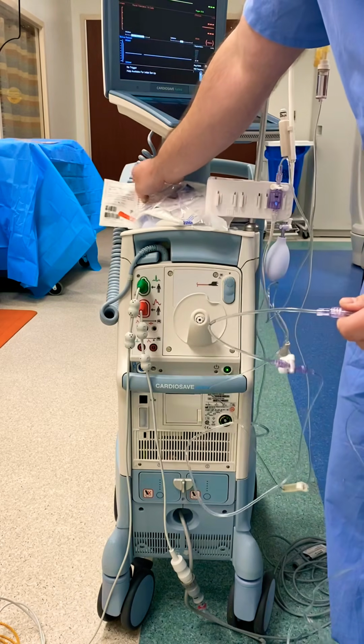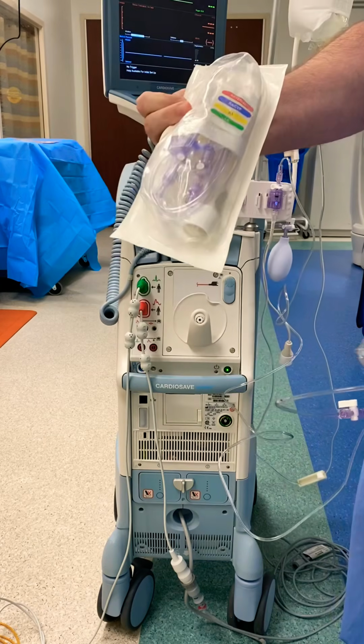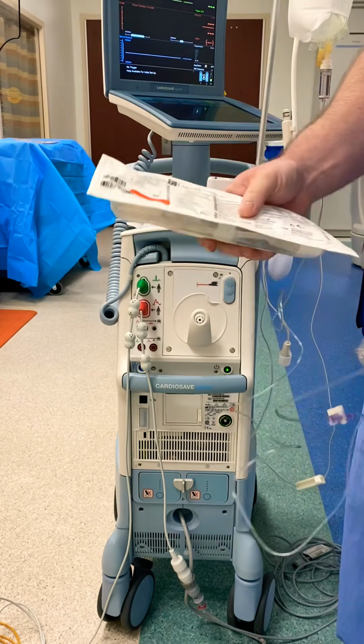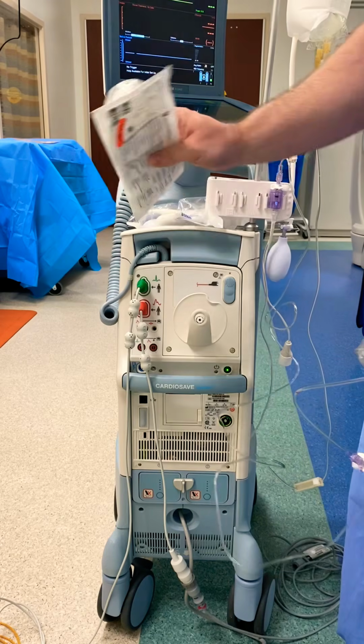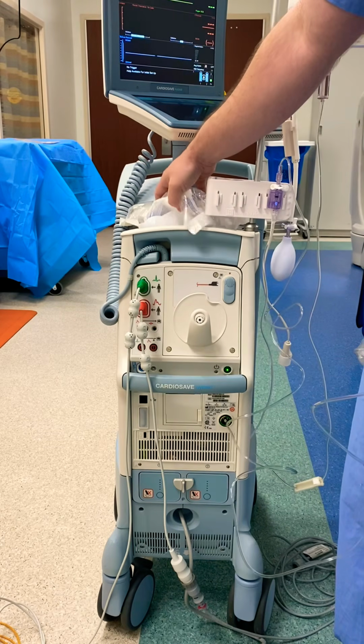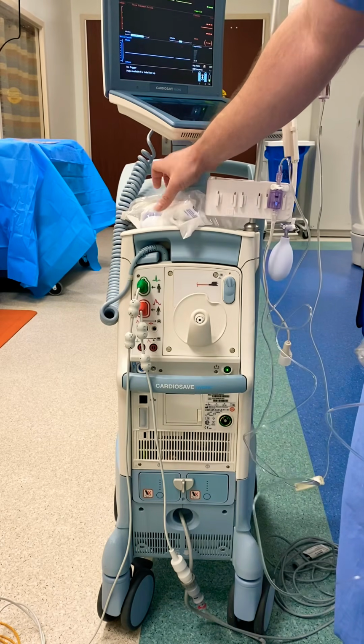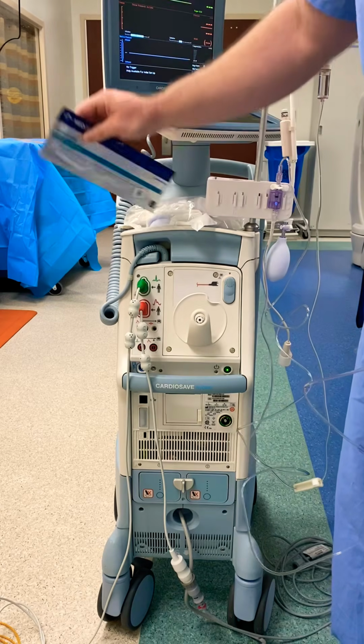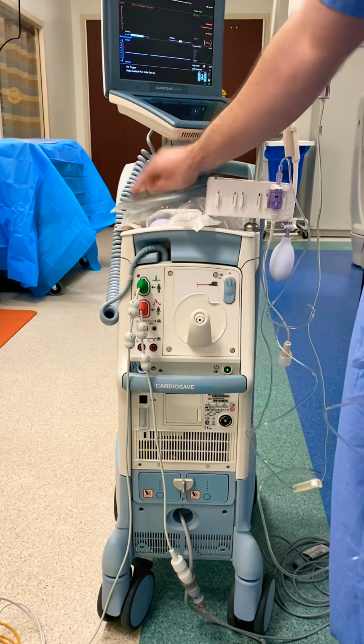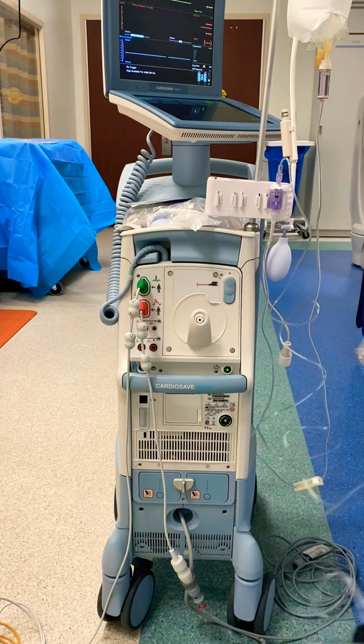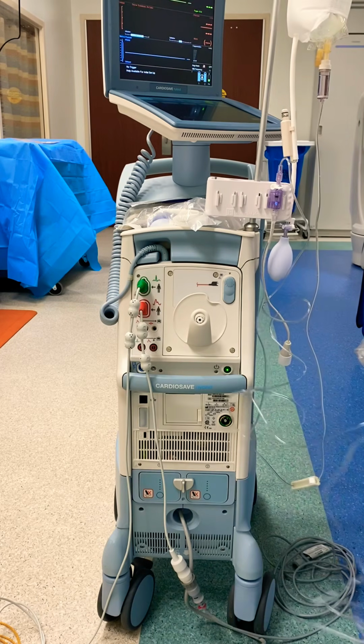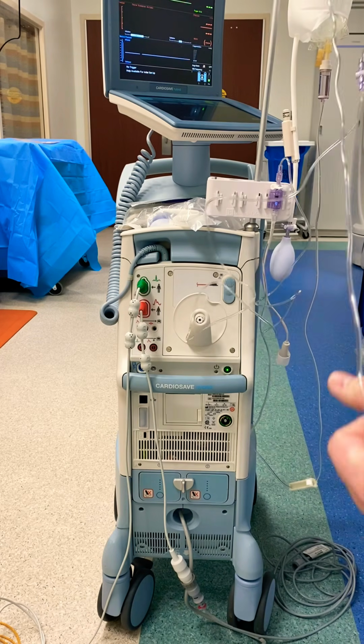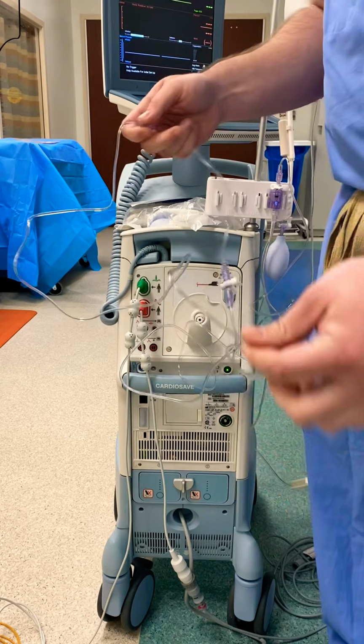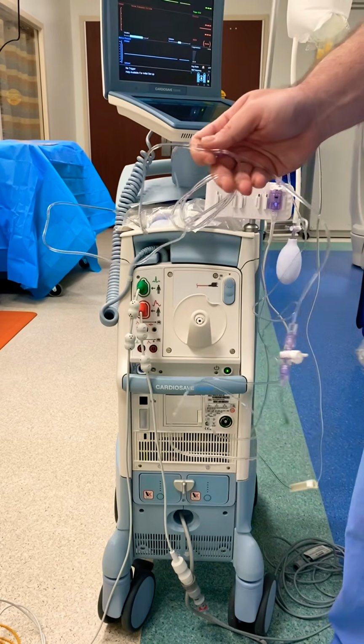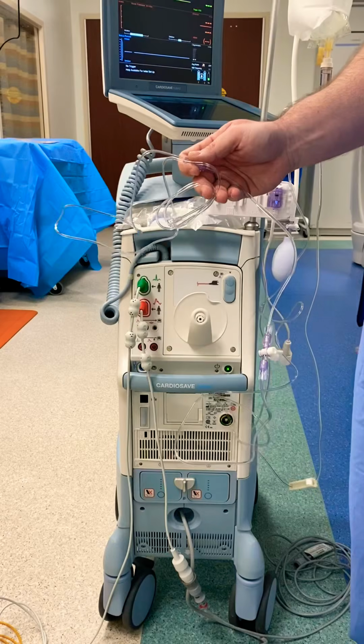This is the kit: it's a single transducer, one spike, hemodynamic monitoring line that we always leave right here on the balloon pump in the hallway. There's also a pressure bag and some radiolucent leads, okay? All of these stay with each pump out in the hall, and it should stay plugged up. This is an extra extension. This is what comes in the balloon pump kit.